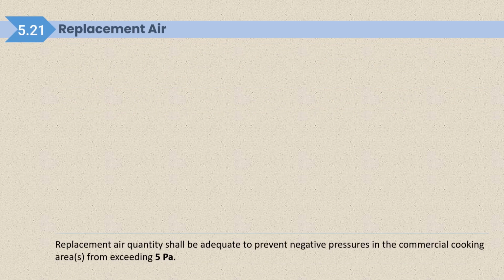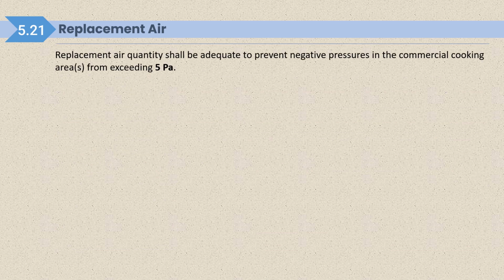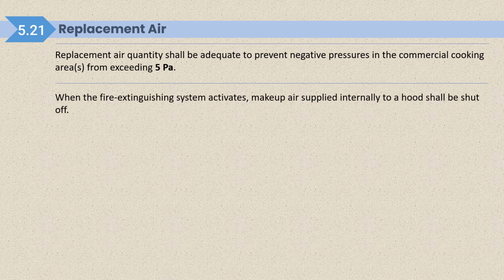Replacement air. Replacement air quantity shall be adequate to prevent negative pressure in the commercial cooking areas from exceeding 5 Pascal. So this is requirement of replacement air, supply air. When the fire extinguishing system activate, makeup air supplied internally to hood shall be shut off. So makeup air supply air will get shut off in case of fire.